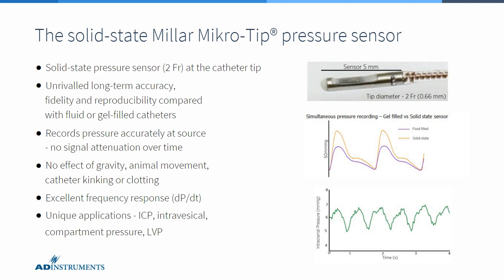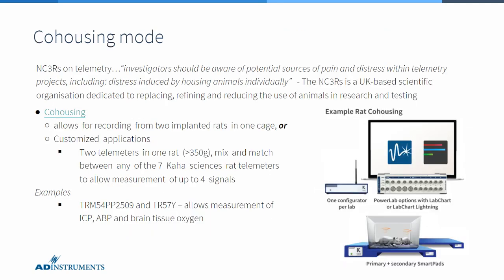You get an excellent frequency response because you're recording directly at source. There's no need for the signal to be transmitted through the gel or fluid, meaning you get an excellent frequency response, which is great for measuring dP/dt accurately from your left ventricular pressure waveform. This also supports unique applications, particularly intracranial pressure, ICP, which I'll talk about in more detail later. This is a really low pressure waveform and can be accurately captured with the rat pressure telemeters.